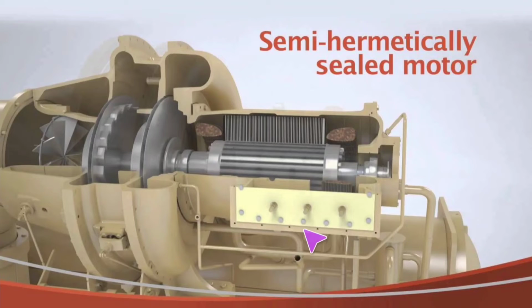Another thing you can see here that's pretty nicely displayed is these right here. This little line, it may be kind of hard to follow. I'll try to explain this better later. Here, we can draw this here. This pipe right here, right there. That pipe is part of the motor cooling circuit. Okay, so this is the drain pipe that the refrigerant that gets pumped into the motor housing drains back through to reintroduce the refrigerant back into the system.